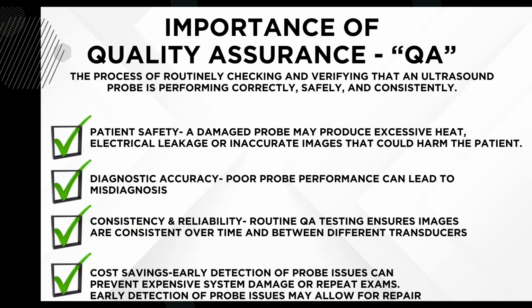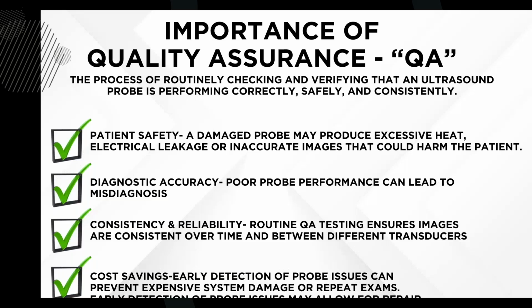All right. So this is on the top here. We got this particular 12L, 12 linear probe on this system. It's frozen right now. When we talk about an air scan, this is typically what it looks like on the system here. We got uniformity across the top of the array here. You see there's no dropout, no elements missing on this particular transducer. I would give it a little wiggle here at the top to make sure that I don't see any issues with the transducer.